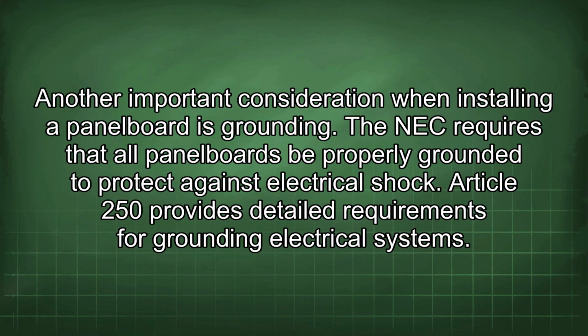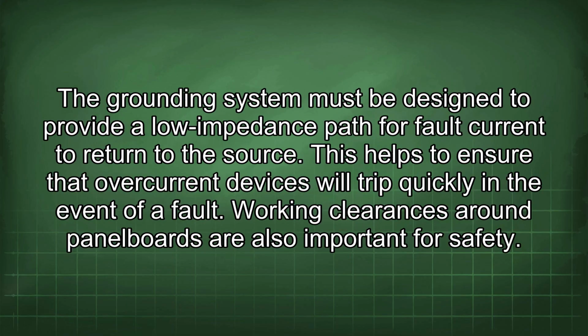Another important consideration when installing a panel board is grounding. The NEC requires that all panel boards be properly grounded to protect against electrical shock. Article 250 provides detailed requirements for grounding electrical systems. The grounding system must be designed to provide a low impedance path for fault current to return to the source. This helps to ensure that overcurrent devices will trip quickly in the event of a fault.